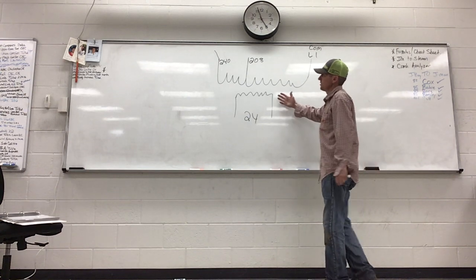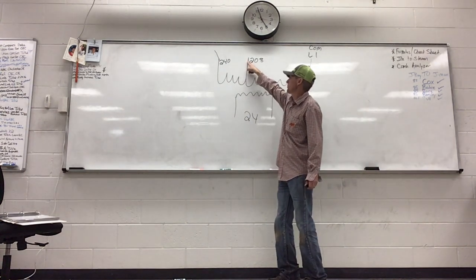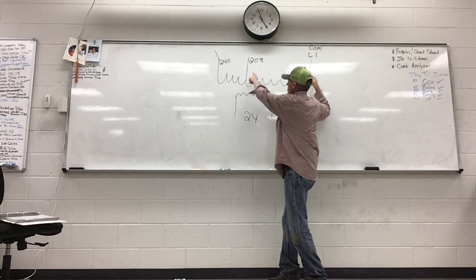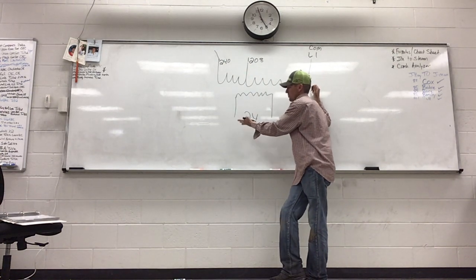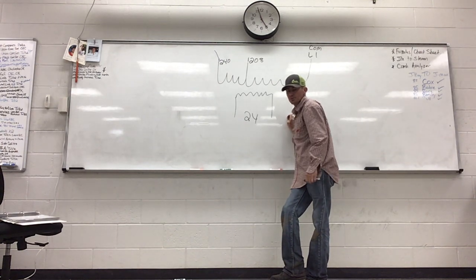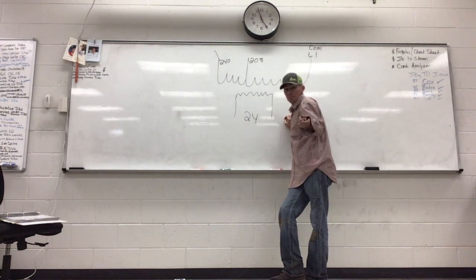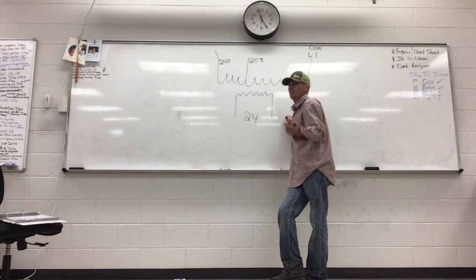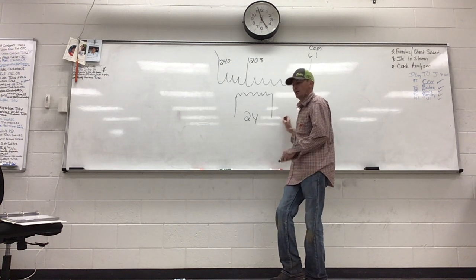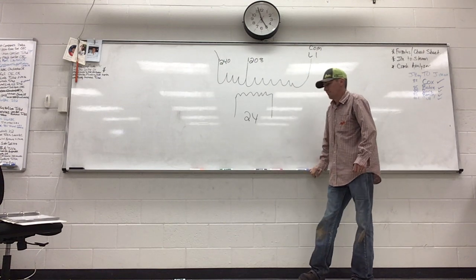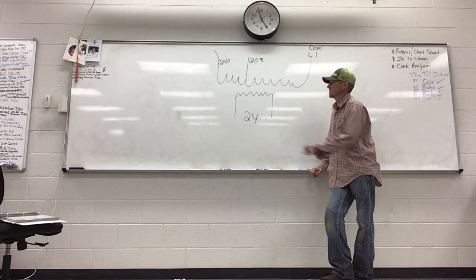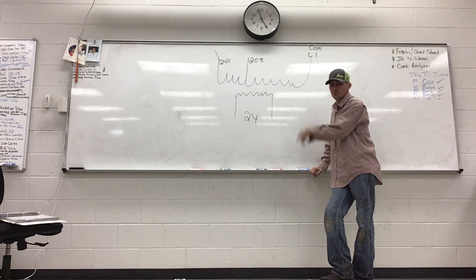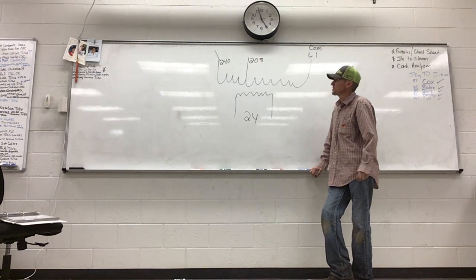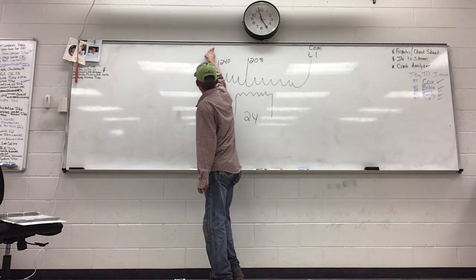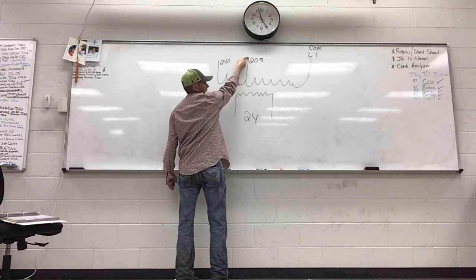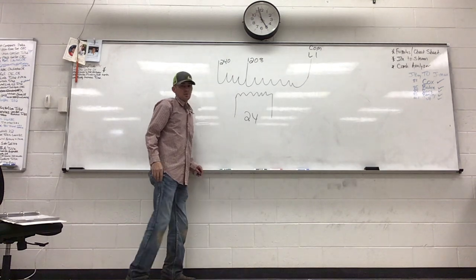But the reason they do that, guys, is so that if they wired them all for 208 out of the factory, and then you put 240 to it, you're going to end up with 29, 30 volts, and then you may end up frying something eventually, right? So if you're doing startups, this is kind of my go-to thing. Here, I'll let you guys in on my secret on startups. The couple main things I see, this is one that drives me crazy. I've seen 10-year-old units that are still whatever, but if it's a 208 building, take this off and move it over here to the 208 tap so that you actually get a true 24 volts coming out.